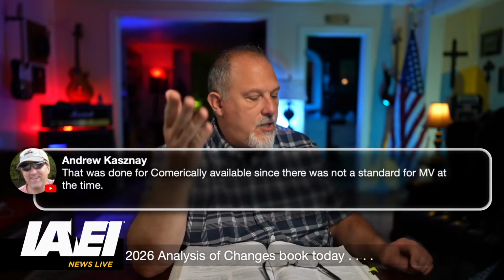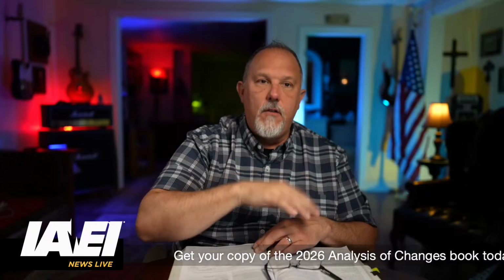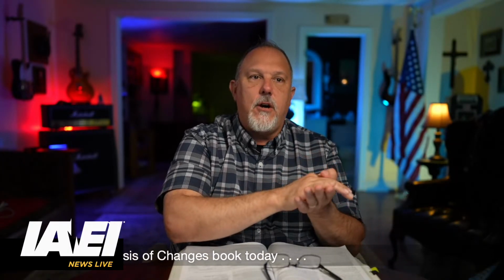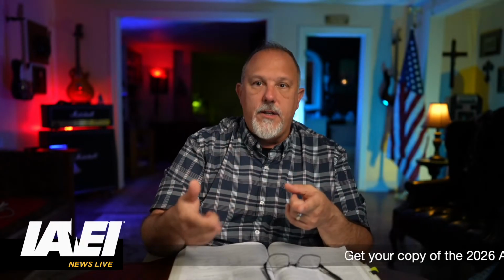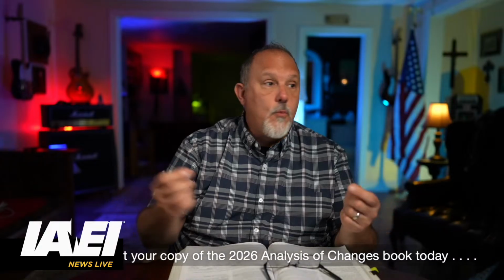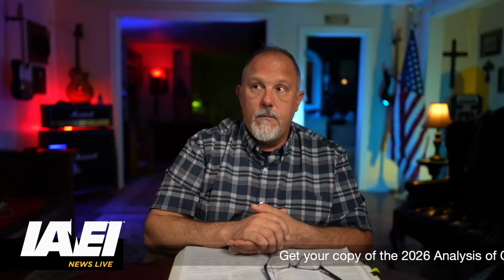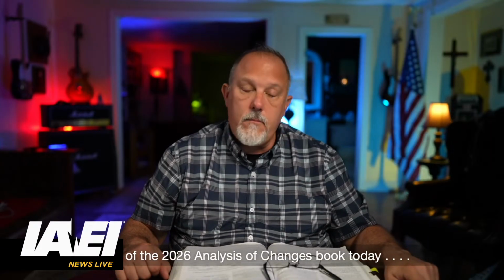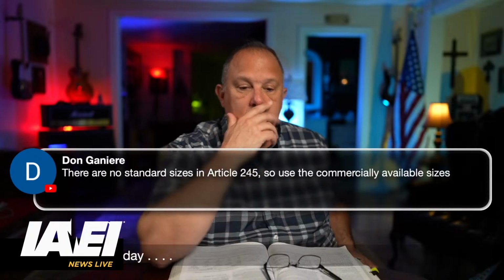So the 240, and I think that's Don, I think that's your point, is that the less than 1,000 volts, the 1,000 volts and less overcurrent protective device standard ampere ratings are governed, and they're in the standards. What Andrew is saying, and I think, Don, what your point was, correct me if I'm wrong, there is no standard, so there would not be a table in 240. So they basically say the next higher commercially available rating, because that could be that's what's available from the manufacturer. Don says there are no standard sizes in Article 245, so use the commercially available sizes.